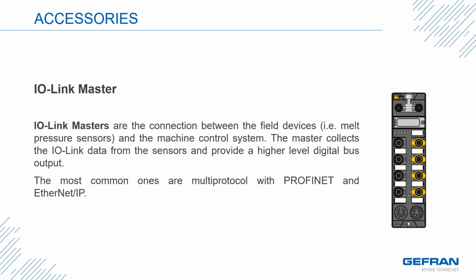The I/O link master is an essential part of the I/O link network. The I/O link masters provide the connection between the field devices like the Gefran I/O link melt pressure sensors and the machine control system. The master collects the I/O link data from the sensors connected and provides it to the higher level digital bus output. Most common ones are a multi-protocol I/O link master that is easily selectable between Profinet and Ethernet IP.